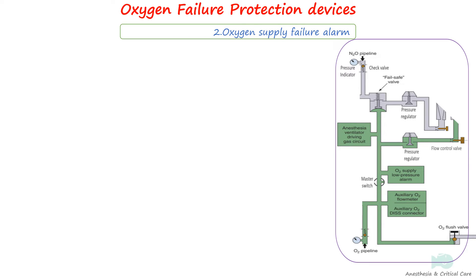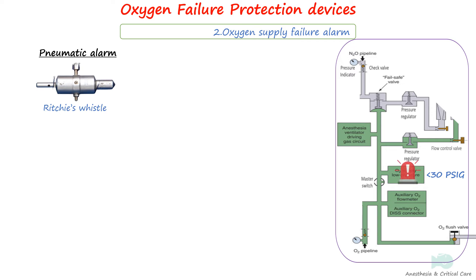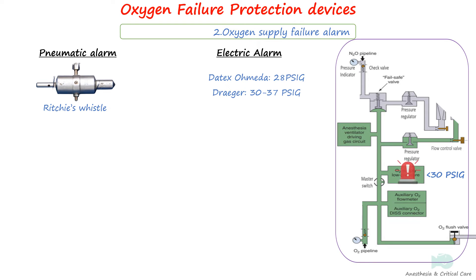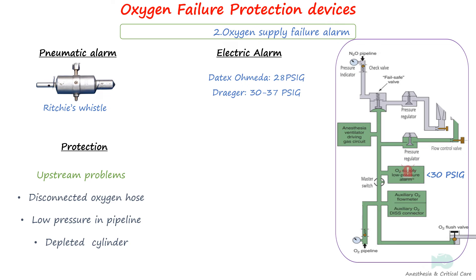The machine standard also specifies that whenever oxygen supply pressure falls below a manufacturer-specified threshold — usually 30 psig — a medium-priority alarm shall sound within 5 seconds, and it should not be possible to disable this alarm. Older alarms like Ritchie's whistle used a pressurized canister filled with oxygen; when oxygen pressure fell below a certain value, the alarm directed the oxygen stream through the whistle. Modern machines employ pressure-operated electric alarms, with Datex Ohmeda triggering at 28 psig and Draeger at 30 to 37 psig. The alarm helps prevent hypoxia caused by problems such as a disconnected oxygen hose, low pipeline pressure, or depletion of the oxygen cylinder.